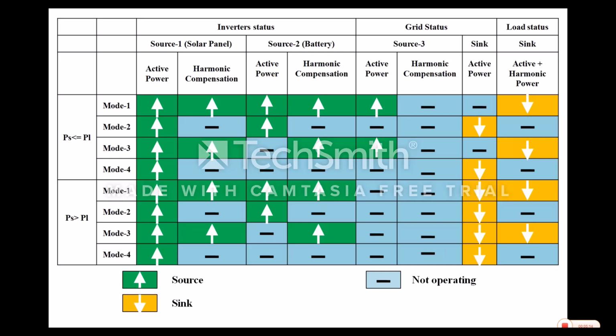Coming to mode 2 operation, there is no nonlinear load, so there is no requirement for harmonic compensation. In mode 1 operation, a nonlinear load is present and draws harmonics, so those harmonics are compensated by the sources, both inverters. In mode 2 operation, there is no nonlinear load present. Whatever the available power, both sources are injected into the grid. You can see there is a light blue-black line indicating the load status and active power status from the grid. It is showing the sink status, and both sources are injecting power.